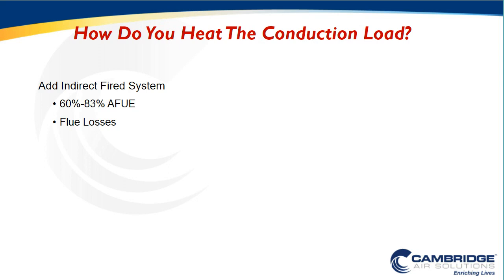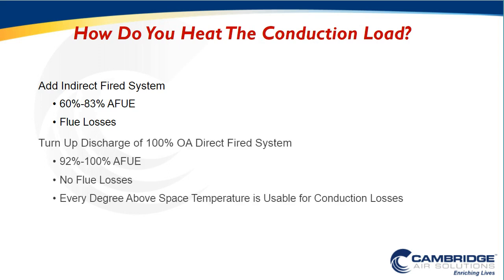But what about this simple concept? What about turning up the discharge of your 100% outside air system and utilizing the 100% combustion efficient, no flue loss combustion process, such that every degree of discharge temperature above space temperature becomes usable heat to counteract any conductive losses? We're talking about energy efficiency here, so this is some pretty simple math. Is 92% greater than 60 to 80? Absolutely. So we're going to try to use the highest energy efficiency combustion process available.